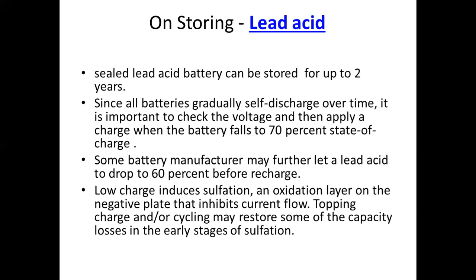So most manufacturers who design batteries, not only lead acid, this particular standard is for lead acid, that is what is being mentioned here. But most manufacturers who make these batteries are doing 60%. Some will leave it at 20 or 30%. That is also considerable based on what electrolyte is being used.